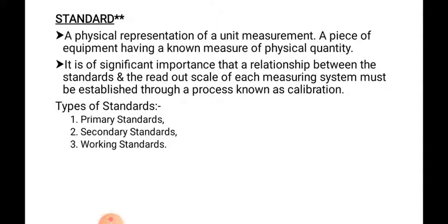For that purpose, every instrument must be calibrated every year, and a certificate of calibration must be given by the calibrating authority. On that basis, every year inspections of the different grocery shops are done, and at the time of inspection, that certificate is taken as the indication of calibration of the particular instruments used at the grocery shop.